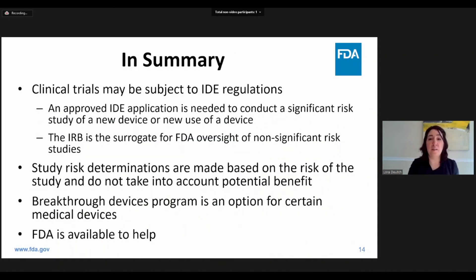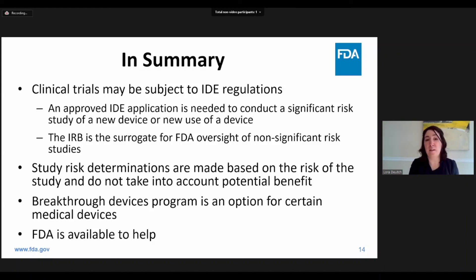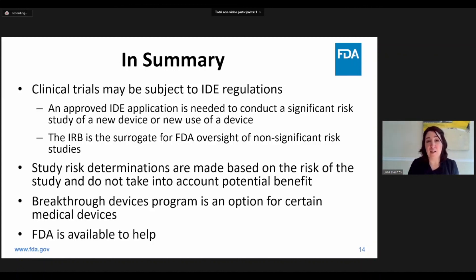To summarize the take-home messages: device clinical trials performed on human subjects may be subject to IDE regulations depending on how the device is being used in the study. An approved IDE application is needed to conduct a study determined to constitute a significant risk to the rights, safety, or welfare of subjects. For trials determined to be non-significant risk, the IRB acts as a surrogate for FDA IDE approval. Study risk determinations are made based on the risk of the study, not on the ratio of benefit to risk. The Breakthrough Program is intended to help patients have more timely access to certain medical devices by expediting their review. The FDA is available to help with study risk determinations or before submission of an IDE application.